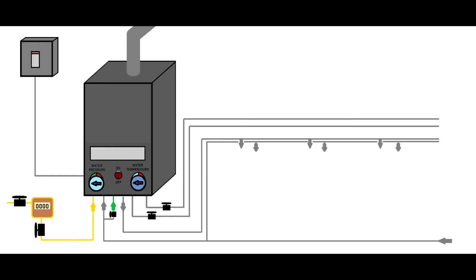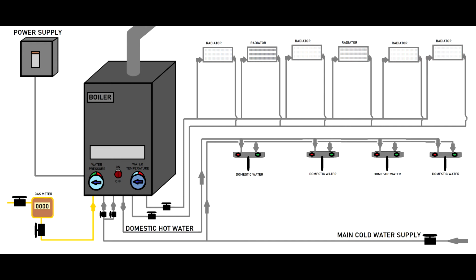This type of boiler is a Combi. It heats the water instantly for domestic water and it has a separate circuit for central heating. After we install the pipes and make sure the volume is well calculated for the water, the pump can support the appropriate circulation, and our main cold water supply has enough pressure to lift the water to whatever floor we want, we fit the pipes and then we install the taps and the radiators. After we do the pressure testing and make sure we don't have any leak, we open the main cold water supply and also the installation filling valve, and the installation is ready to go.